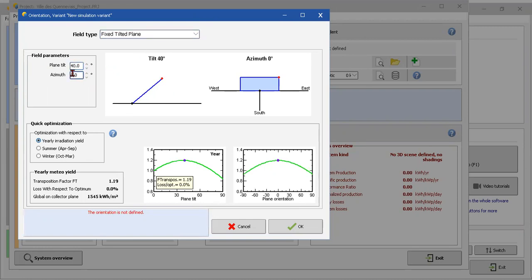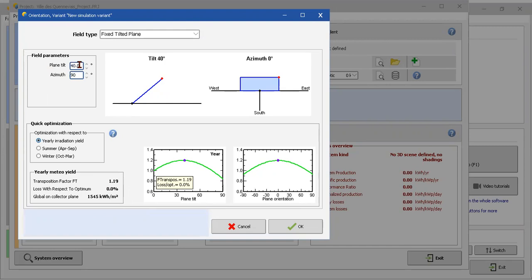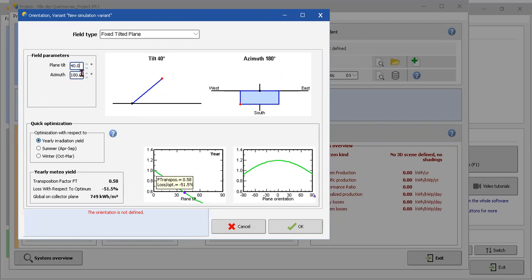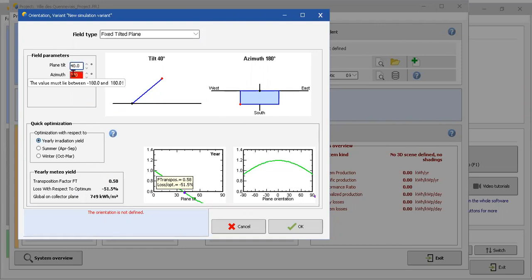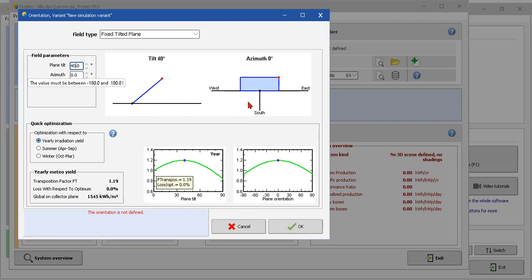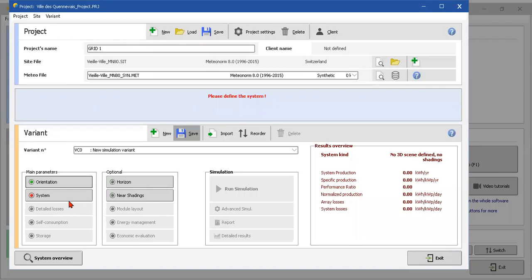And here we have - this is important - the loss with respect to optimum. This depends on the plane tilt and the azimuth. So this is just to play a little bit. If we have 45 here, we're gonna lose 0.6%. We have 65, we're gonna lose a lot. So the tilt should be less than 30, 40. With 40 is easier - 0%. Azimuth, 90 - no. Okay, I guess azimuth 0. Yes, I'm just checking here. Yes, okay, 0. North is azimuth 180. Coming from here, clicking okay.